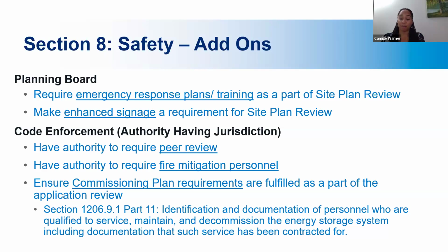Currently, the fire code gives AHJs the authority to require the developer pay for independent peer review of a permit application, but this isn't typically utilized. We highly recommend that peer reviews be mandatory for all battery energy storage installations to ensure compliance and oversight for upcoming projects.